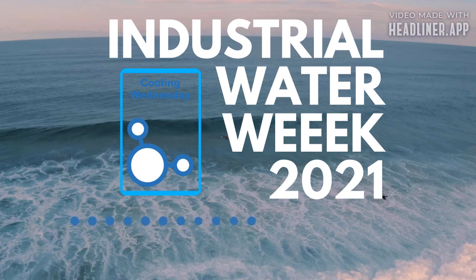So a water meter that you would buy would have some sort of contactor in it. And after so many gallons, it sends a pulse back to the controller, and the controller is then set up via you to know every time it gets a pulse, it's 10 gallons or 50 gallons or 100 gallons. And now you've done your math, and you said for every so many gallons, we're going to energize the pump relay to come on for a specific amount of time, and that's going to precisely treat all that new water that came in. So that is feeding based on demand, and that's one of my favorite ways to do that.